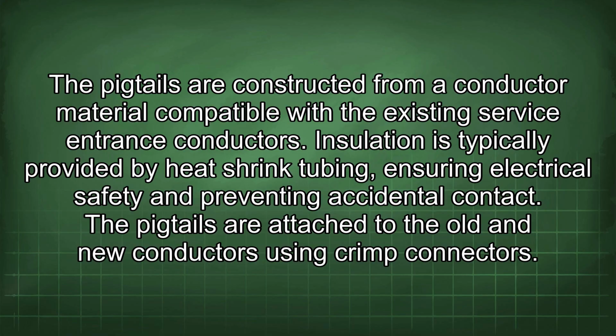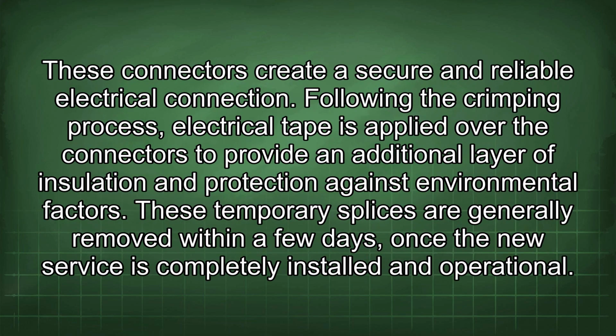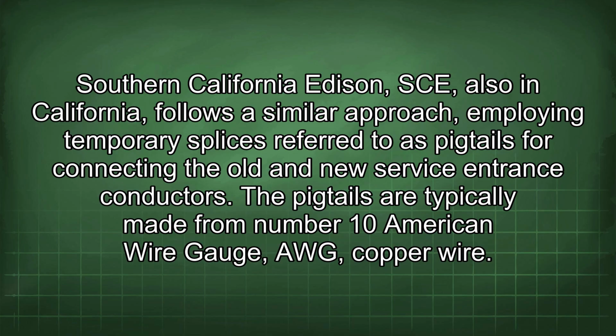The pigtails are attached to the old and new conductors using crimp connectors. These connectors create a secure and reliable electrical connection. Following the crimping process, electrical tape is applied over the connectors to provide an additional layer of insulation and protection against environmental factors. These temporary splices are generally removed within a few days once the new service is completely installed and operational. Southern California Edison, also in California, follows a similar approach, employing temporary splices referred to as pigtails for connecting the old and new service entrance conductors.